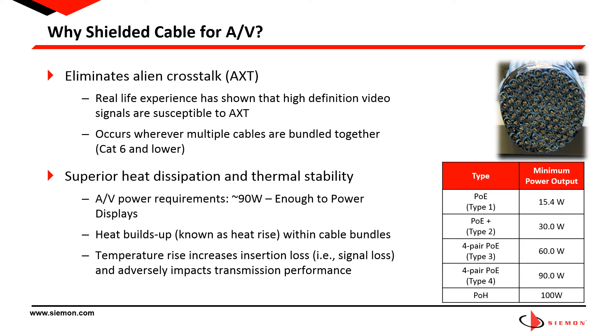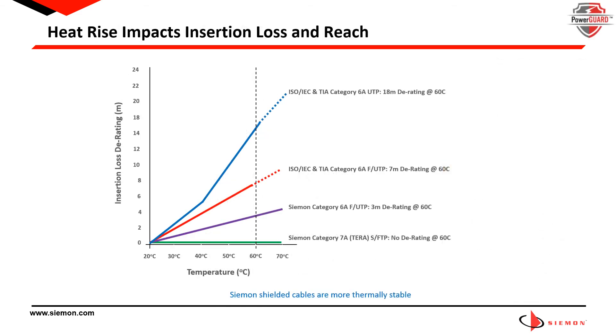While this is good news, there are some considerations you need to be aware of. When DC power is delivered over the cabling to end devices, heat builds up, which is known as heat rise. This is even more of a concern within cable bundles because the heat cannot dissipate from the cables in the center of the bundle. This temperature rise increases insertion loss, which is signal loss, and adversely impacts transmission performance. With higher power Type 3 and Type 4 PoE, heat rise in bundles is more of a concern, which is why ISO, IEC, TIA, and the National Electric Code or NEC in the United States all have guidelines for reducing bundle size in higher-than-60-watt PoE based on gauge size, operating temperature, and conductor ampacity. To offset insertion loss caused by heat buildup, overall channel length may need to be reduced — this is known as length derating in industry standards. To prevent heat buildup within cable bundles, the size of the bundles may also need to be reduced.